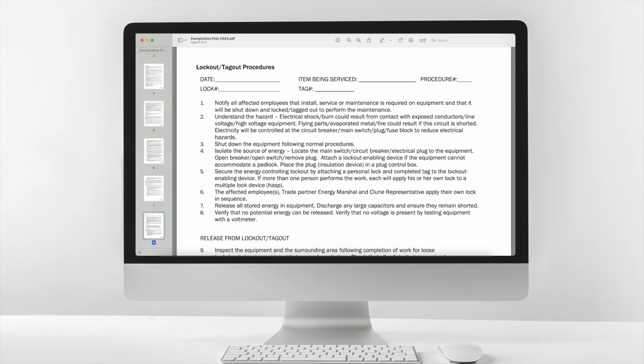5. Secure the energy controlling lockout by attaching a personal lock and completed tag to the lockout enabling device. If more than one person performs the work, each will apply his or her own lock to a multiple lock device, HASP. 6. The affected employees, trade partner Energy Marshal and Clune representative apply their own lock in sequence. 7. Release all stored energy in equipment. Discharge any large capacitors and ensure they remain shorted. 8. Verify that no potential energy can be released. Verify that no voltage is present by testing equipment with a voltmeter.